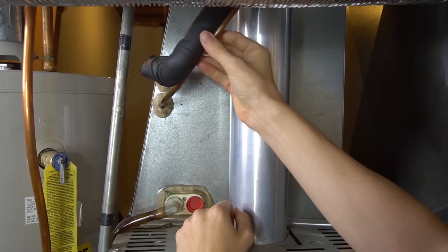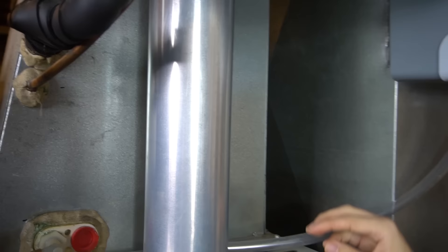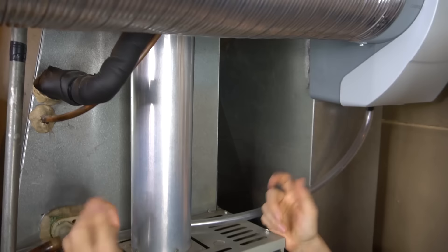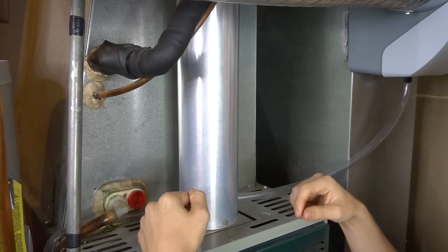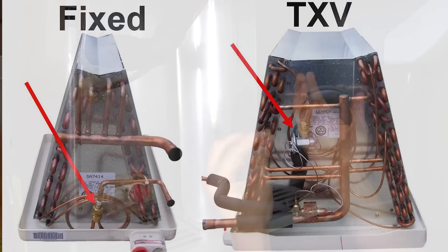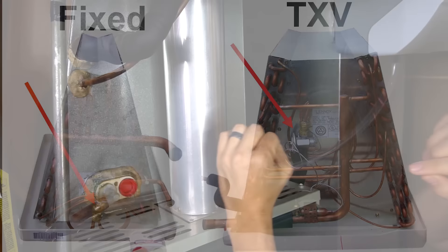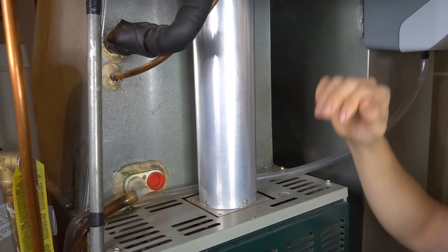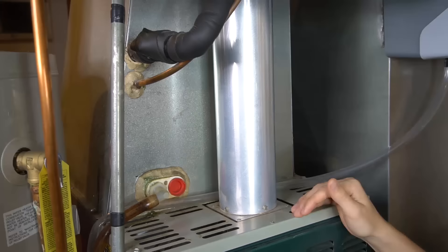Here's the line set — the same two pipes we saw outside — going into the evaporator coil behind the metal. Another important component is the metering device, which is also behind the sheet metal. There are a few types: a fixed orifice, which can be a piston or capillary tubing, or a TXV metering device, which is automatic and regulates refrigerant flow automatically. In simple terms, the metering device is a very small hole — as the compressor forces high-pressure refrigerant through that small hole, it becomes low-pressure refrigerant. The purpose is to drop the refrigerant pressure and cause a restriction in the liquid line.